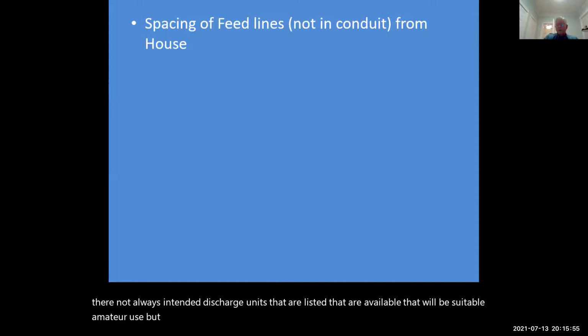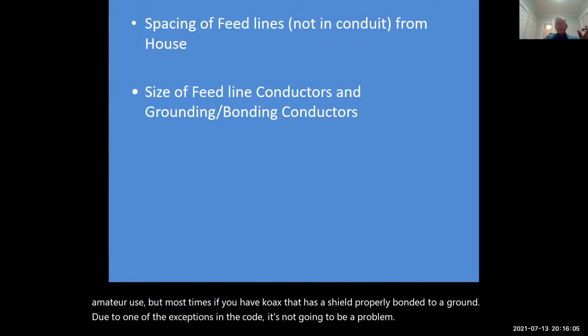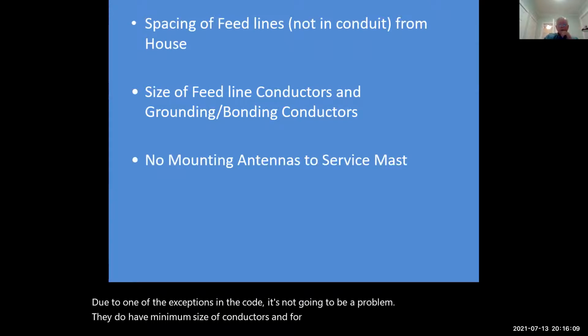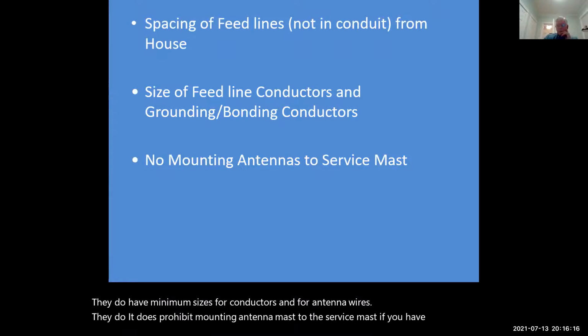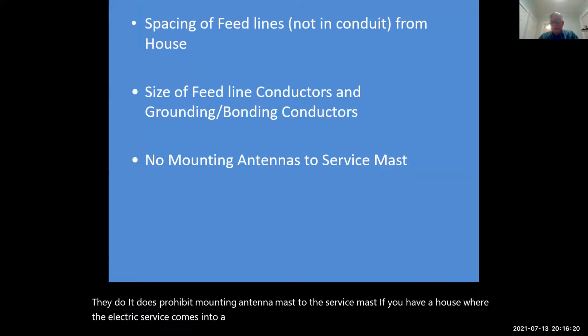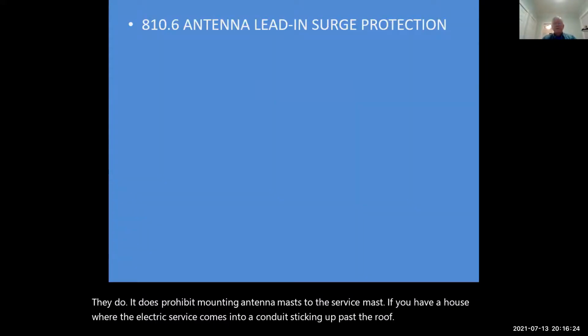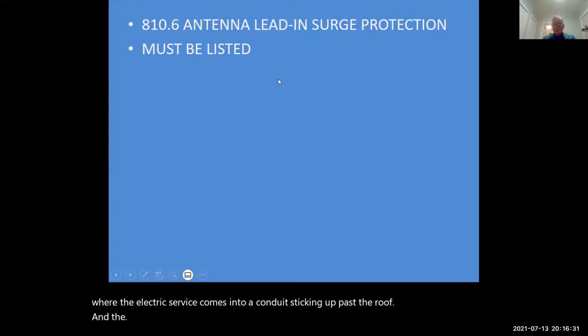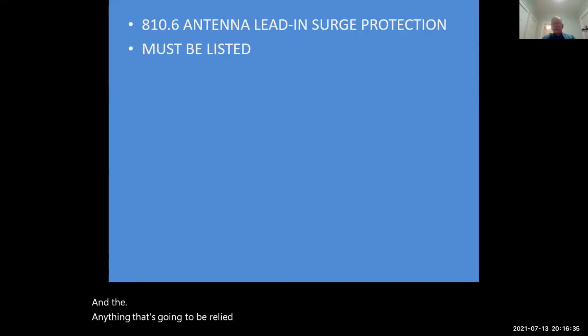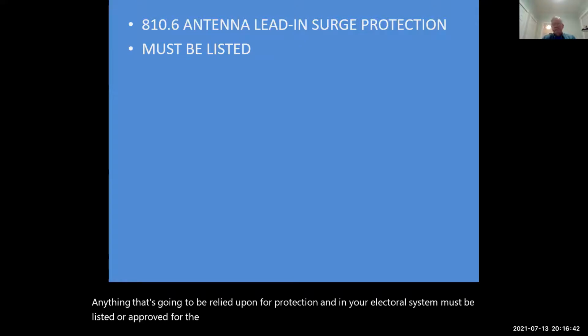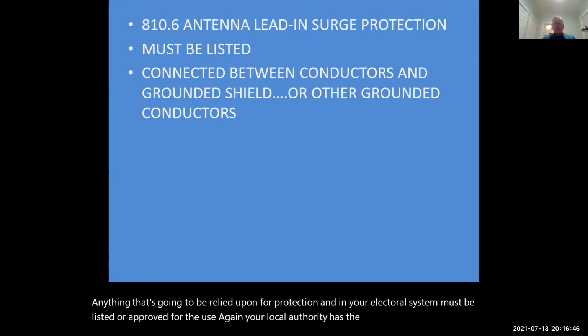But most times, if you have coax that has a shield properly bonded to a ground, due to one of the exceptions in the code, it's not going to be a problem. They do have minimum sizes for conductors and for antenna wires. It does prohibit mounting antenna masts to the service mast, if you have a house where the electric service comes into a conduit sticking up past the roof. And anything that is going to be relied upon for protection in your electrical system must be listed or approved for the use. Again, your local authority has the ability to approve or disapprove things.